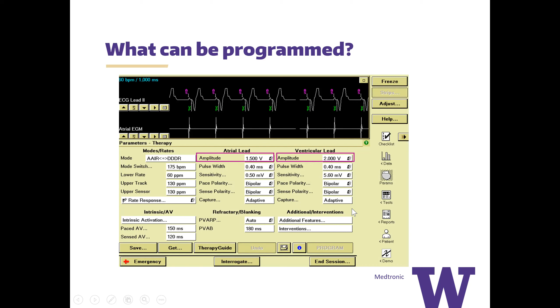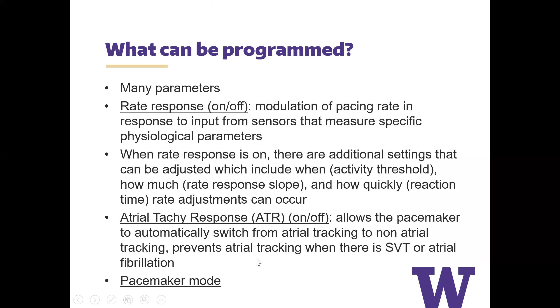Now, when rate response is programmed on, there are additional settings that can be adjusted, and those include the activity threshold, how much rate response slope, and how quickly, which is the reaction time, rate adjustments can actually occur. Atrial tachy response can be programmed on and off. This allows the pacemaker to automatically switch from an atrial tracking to a non-atrial tracking mode, and that prevents atrial tracking when there is, for instance, SVT or atrial fibrillation.